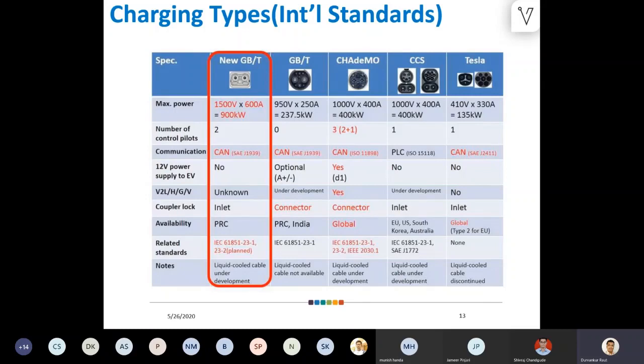Related standards are IEC 61851, clause 23-1 and clause 23-2. A liquid cooled cable is under development, because with 600 amperes current flowing through the wire, you either need a very big wire size, or you can survive with smaller wire diameter by accommodating water cooling or liquid cooling. So charging cables for all these standards with very high current mostly have liquid cooled charging cables.